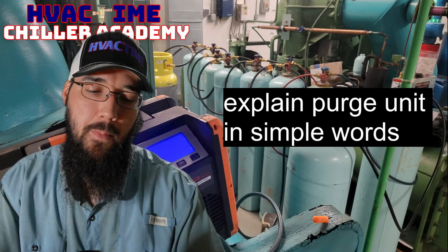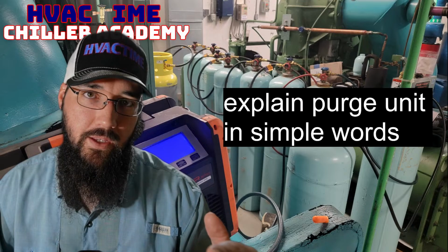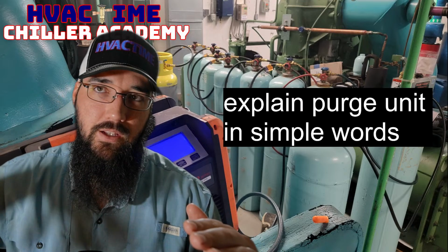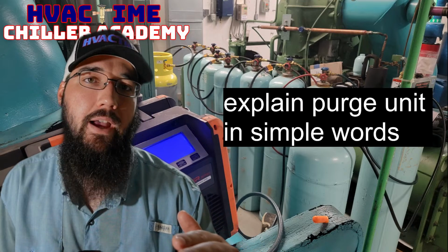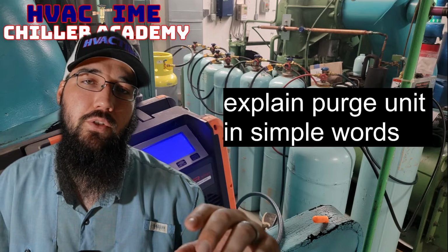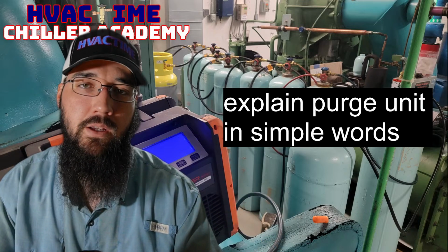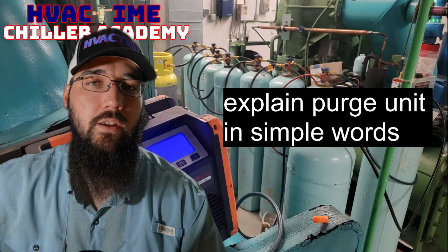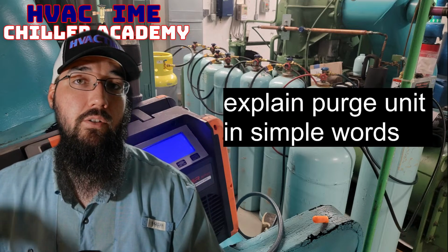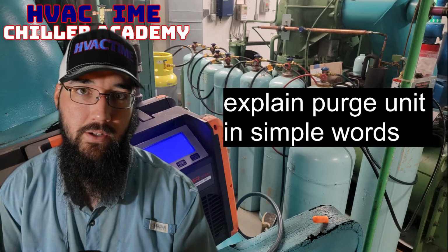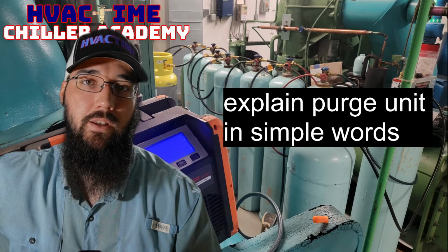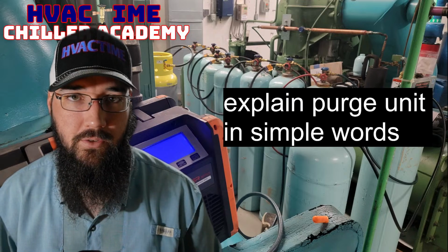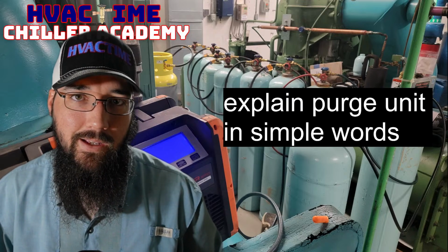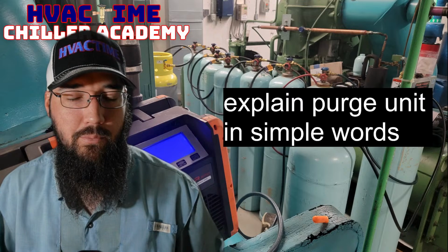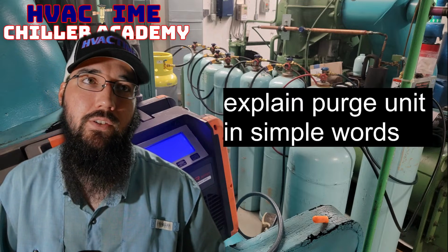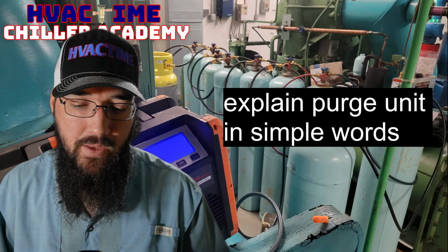Very simple terms here. And so when they separate, the refrigerant is able to go back into the chiller, and then we're able to use a little pump that can suck the non-condensables out of the little chamber that it stacks all this in. That's how it can remove those non-condensables. Now, let's take this a step further and bring it into relevancy on the recovery side.